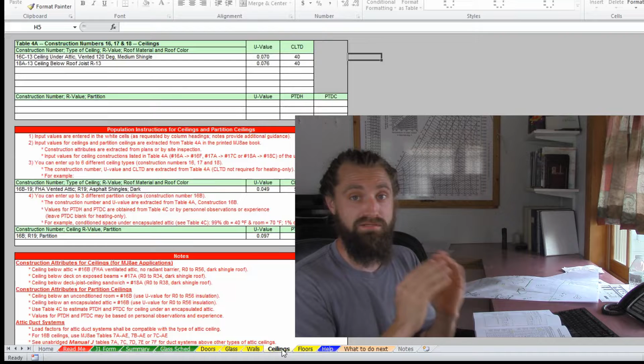Our 16A construction number, which in this book is page 362, that first table is associated with a ceiling under an attic, but if that attic space is 150 degrees—say you didn't have a radiant barrier and you had dark shingles, and it was 150 degrees in that attic when the outside temperature is 95—then this is the table you are looking at.